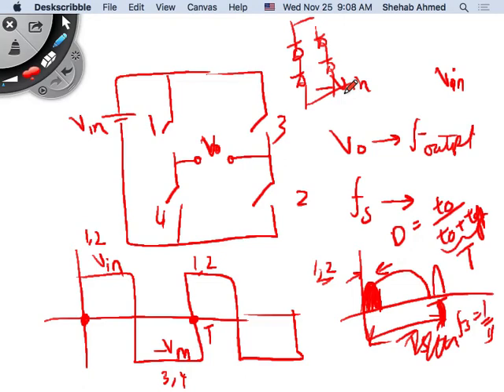So you can take this inverter and supply an AC load, and no problem, it will work. The benefit here is I'm switching at a very low frequency, so my switching losses, turn-on and turn-off switching losses, are very low, and I'm supplying an AC waveform. It's nice, it's great, but I have a lot of harmonic content, right?